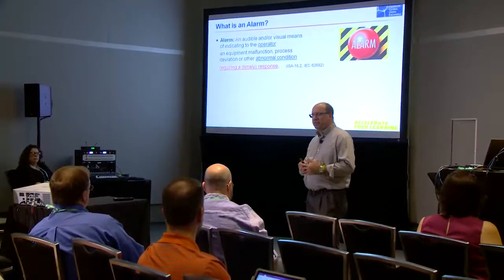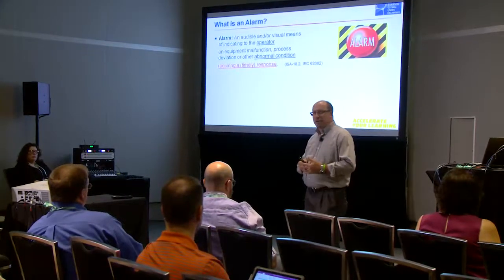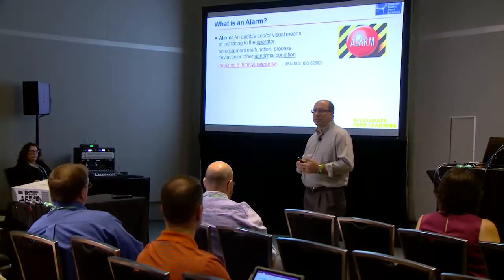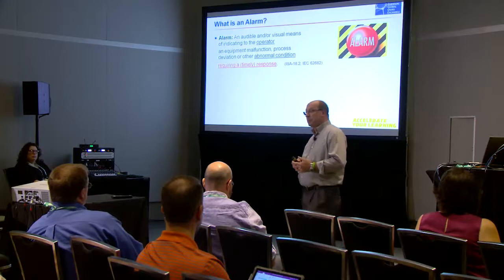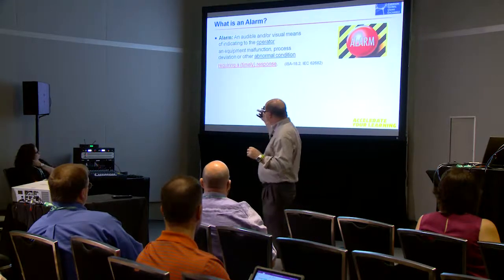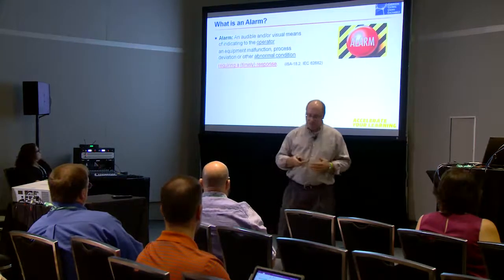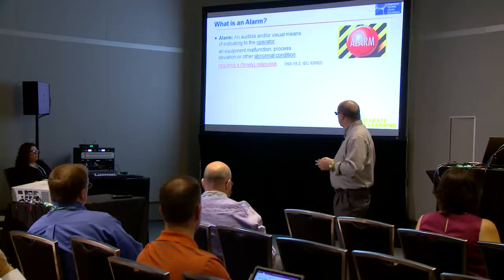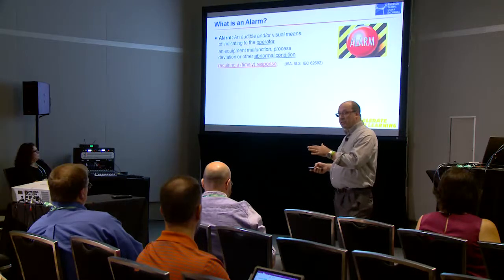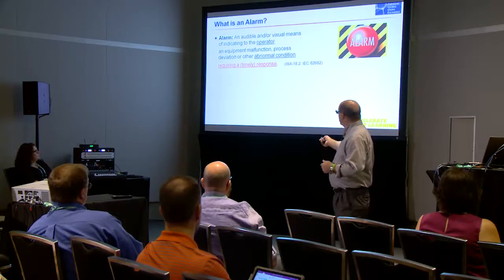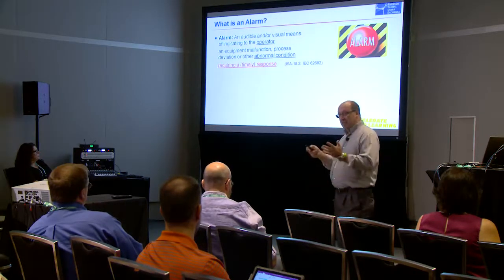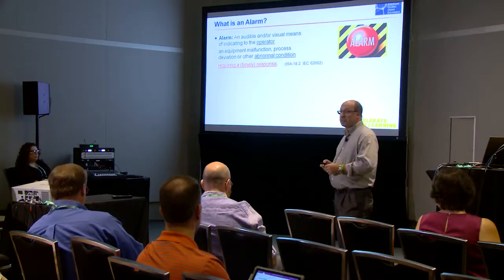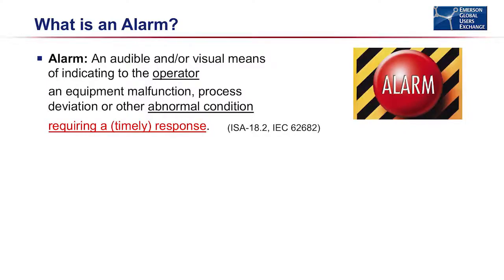Again, if we look at the sump pump example, was there an operator action required in that case to respond to that alarm? No, there wasn't. So you can see that that alarm did not comply with the definition. So it shouldn't have been an alarm in the first place, and that was part of what led to the incident. The idea of going and looking at your alarms and comparing them to what this definition says is a process that's called alarm rationalization, which we'll talk about more in a little bit.